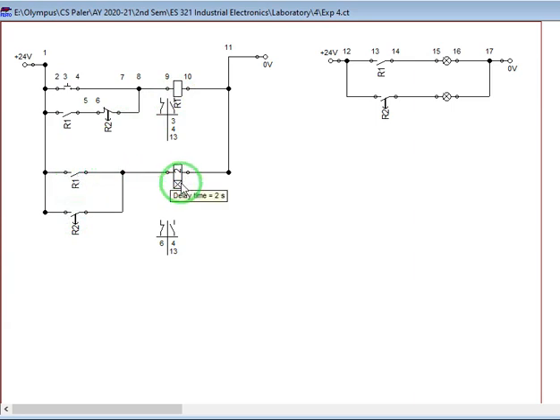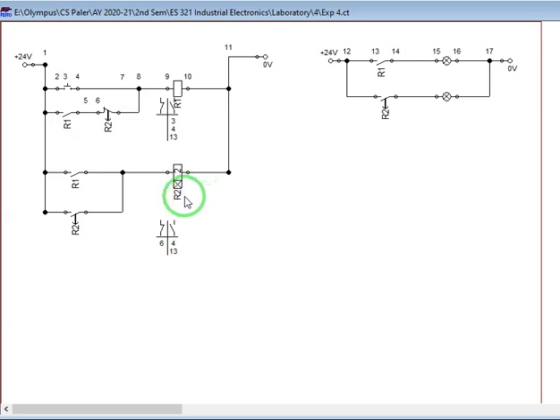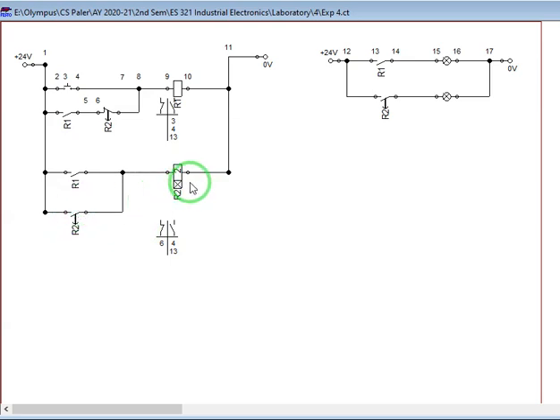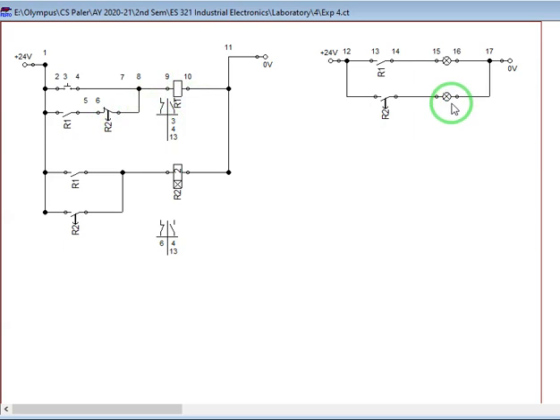But since this is on delay, it will wait for two seconds before R2 will turn on. So when that happens, this R2 will also close, latching our R2. And this will open in such manner that this will unlatch. This will open. So lamp 2 will turn on and lamp 1 will turn off.